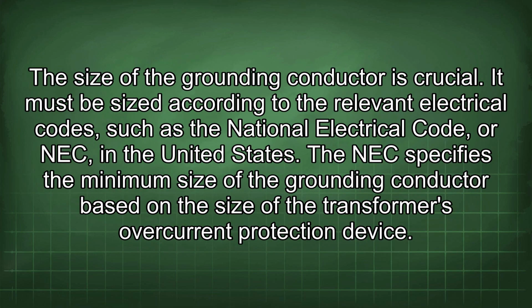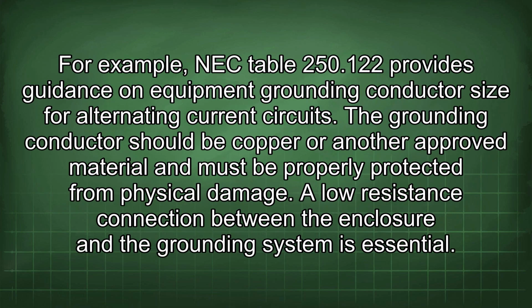The size of the grounding conductor is crucial. It must be sized according to the relevant electrical codes, such as the National Electrical Code, or NEC, in the United States. The NEC specifies the minimum size of the grounding conductor based on the size of the transformer's overcurrent protection device. For example, NEC Table 250.122 provides guidance on equipment grounding conductor size for alternating current circuits. The grounding conductor should be copper or another approved material and must be properly protected from physical damage.